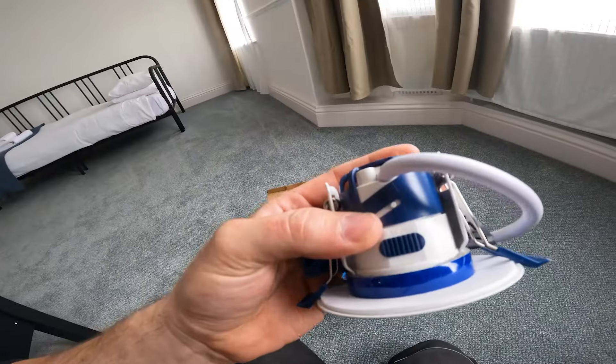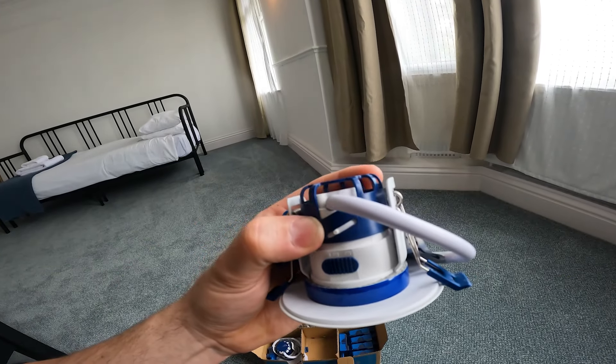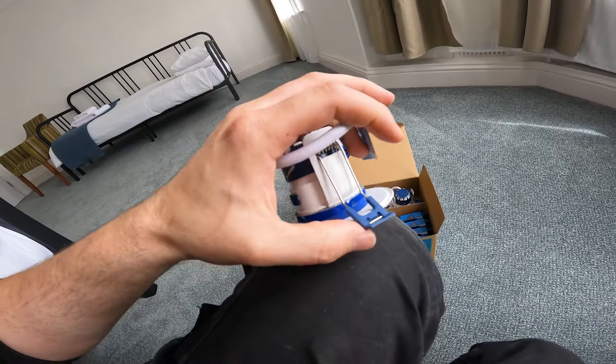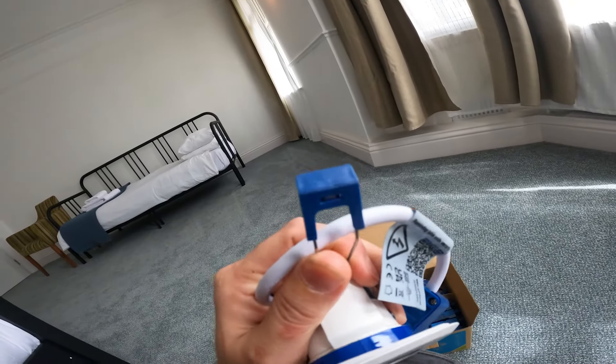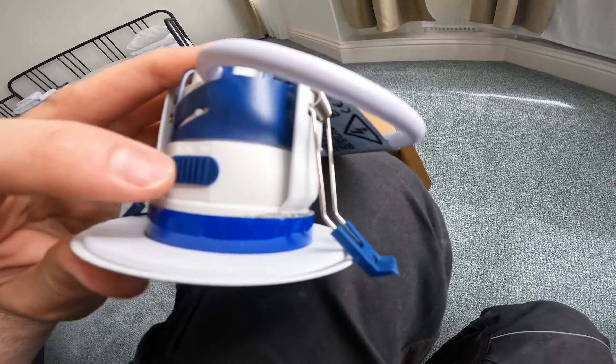Looking at the product itself, it's got a little fire hood cap. So if you've got some insulation up there, you can basically twist this little bezel and that'll give you a bit more height and a bit more airflow around your downlight. It's also got these rubber feet. A lot of downlights you see have just a metal spring, but they've taken that metal piece and added nice wings on it, so it doesn't just bust into your plaster trying to get them in and out. You've got a nice little wedge and feet, so it should be nice and plasterboard-friendly instead of ripping two little lines across the ceiling. You've also got the option of 6.4 watt or 4 watt - just a little flick of the switch.